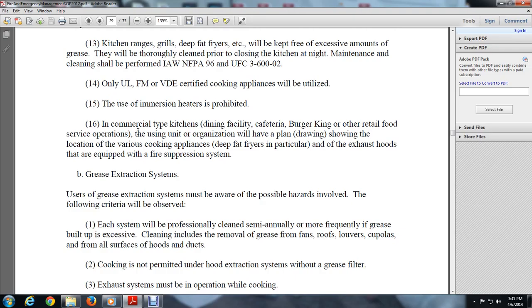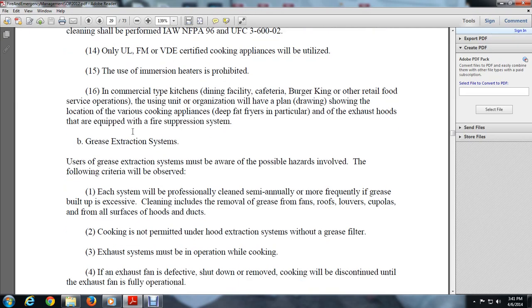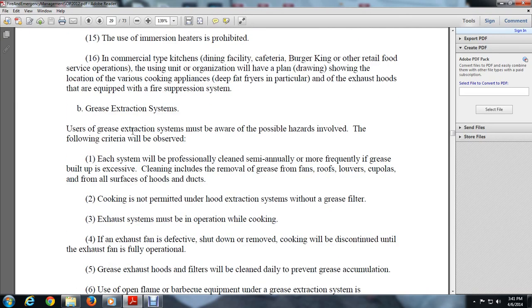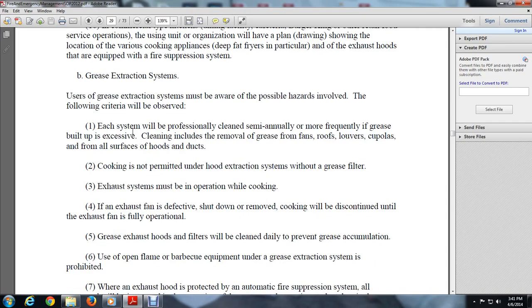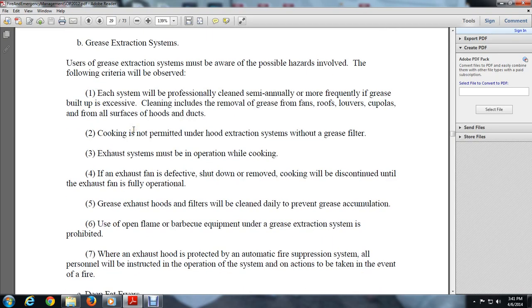1. Each system will be professionally cleaned semi-annually, or more frequently if grease builds up, including the removal of grease from fans, roofs, louvers, and cupolas, and from all surfaces of the hoods and ducts. 2. Cooking is not permitted under the extraction system without the grease filters. 3. The exhaust system must be operating during cooking. 4. If the exhaust fan is defective, shut it down. Cooking will be discontinued until the exhaust fan is fully operational. 5. Grease exhaust hoods and filters will be cleaned daily to prevent grease accumulation. 6. Use of open flame barbecue equipment under the grease extraction system is prohibited.